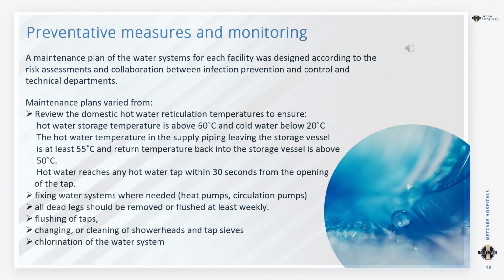Our maintenance plans varied from reviewing the domestic hot water reticulation temperatures to ensure that the hot water storage temperature is above 60 degrees and cold water was below 20 degrees. The hot water temperature in the supply piping leaving the storage vessel is at least 55 degrees, and on return temperature back to the storage vessel is above 50 degrees. This was not always easy to achieve, especially in larger facilities or older facilities where we've had plumbing issues. Hot water reaches any hot water tap within 30 seconds from the opening of the tap.